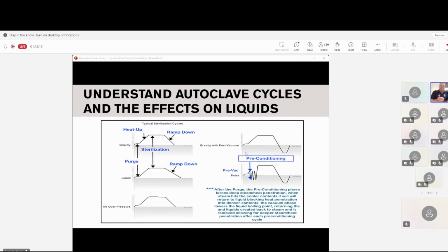When it pulls a vacuum, you lower the temperature of the boiling point. So you're pulling 29 inches, your boiling point is 54 C or 129 degrees. Now that liquid barrier that was in your way has turned back to a gaseous state, a misty, gassy state, and that blockage is now removed. So as it comes down and pulls all the way down, all the liquids are gone. They're boiled and turning to gas.